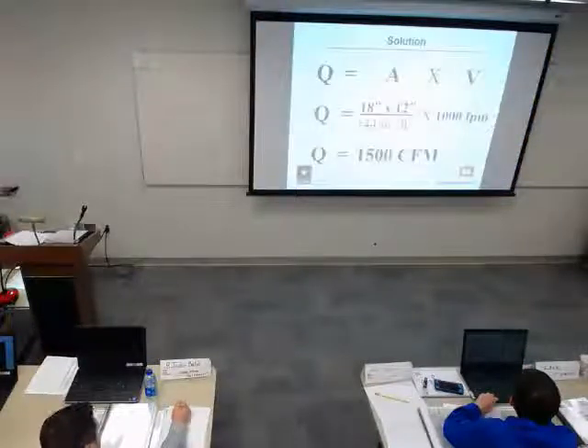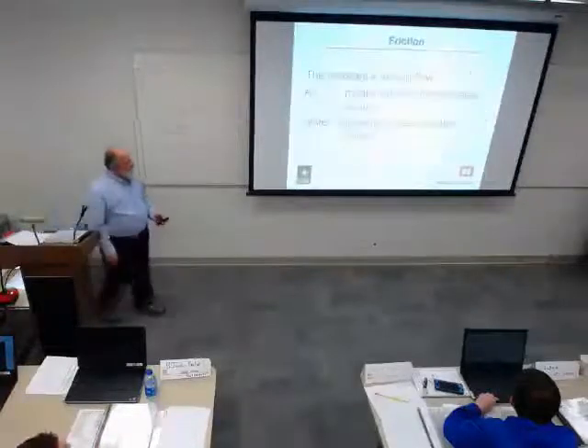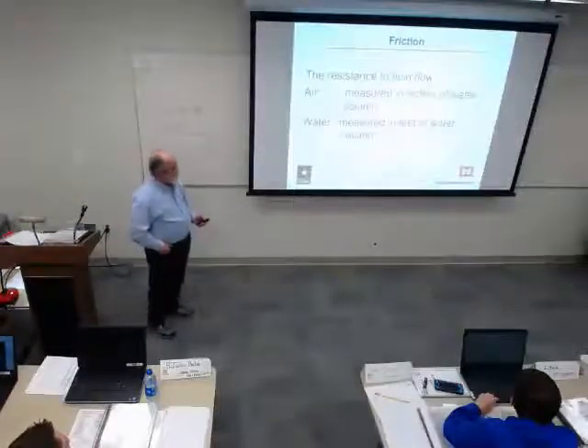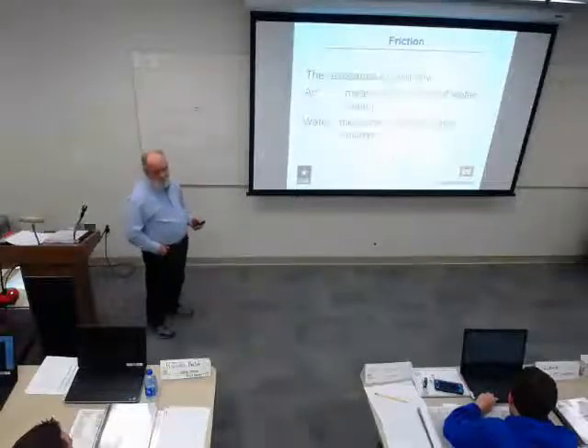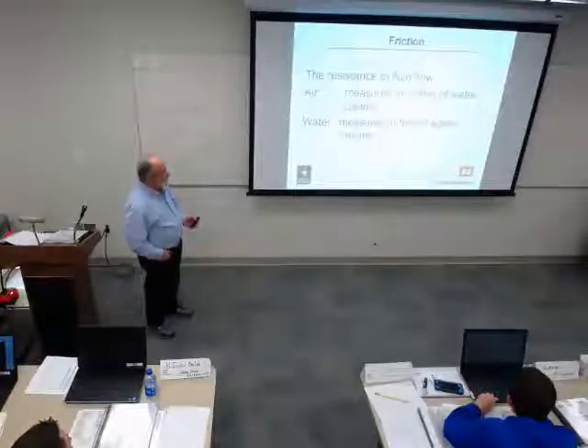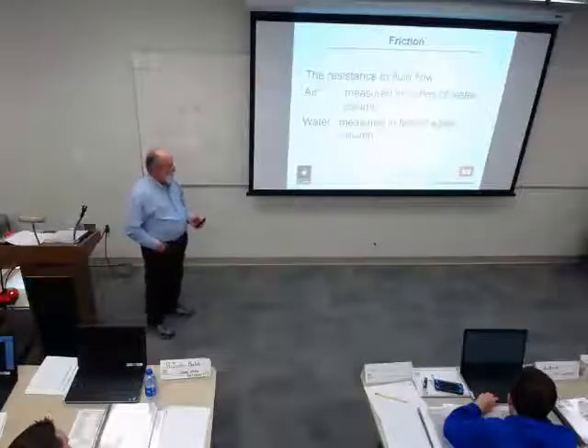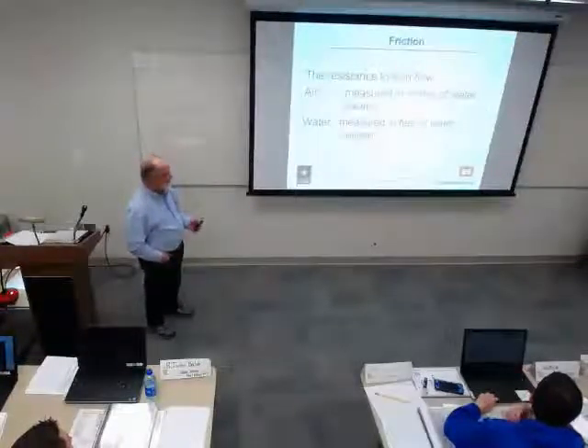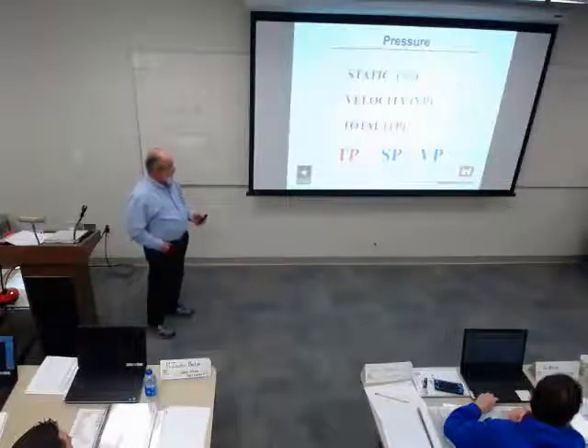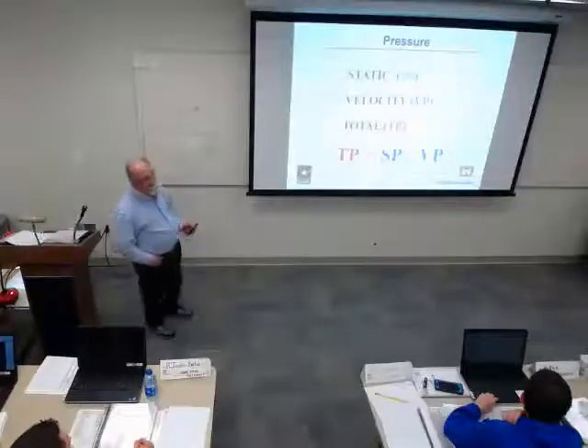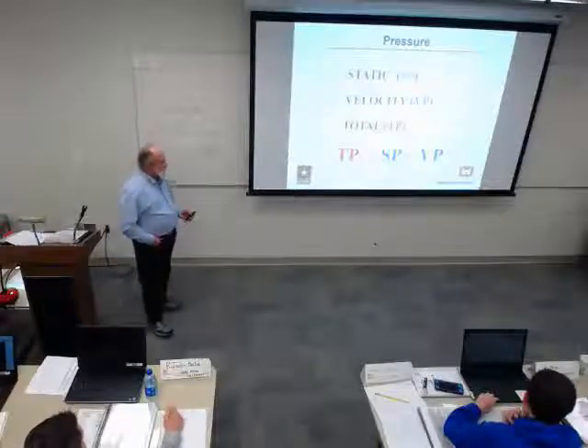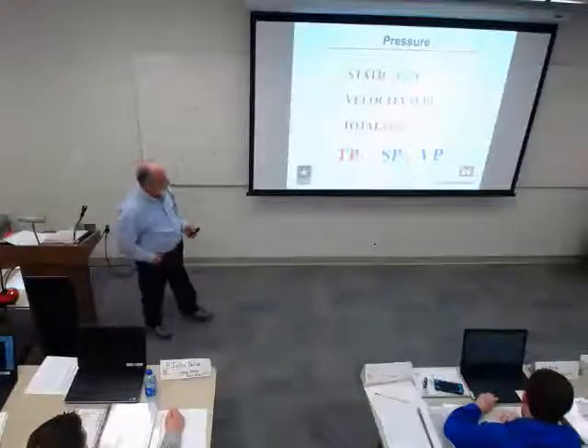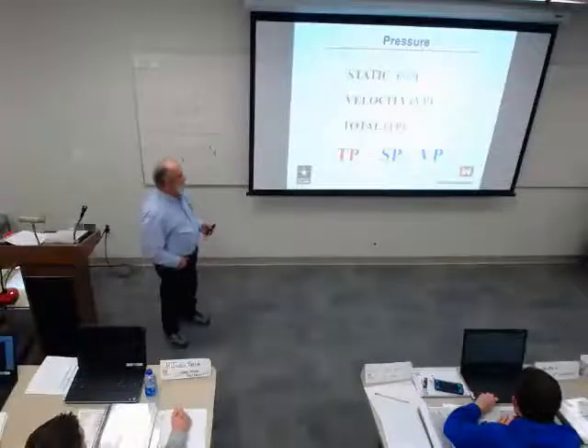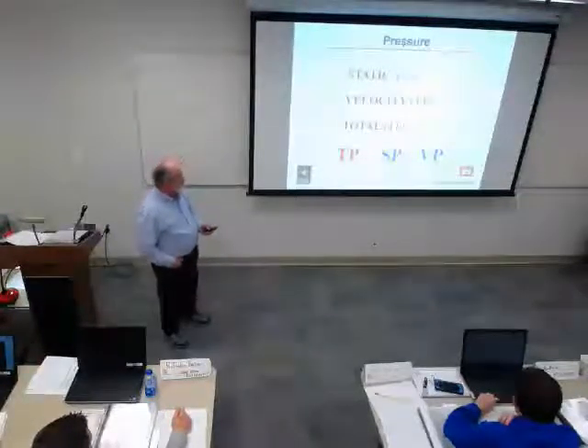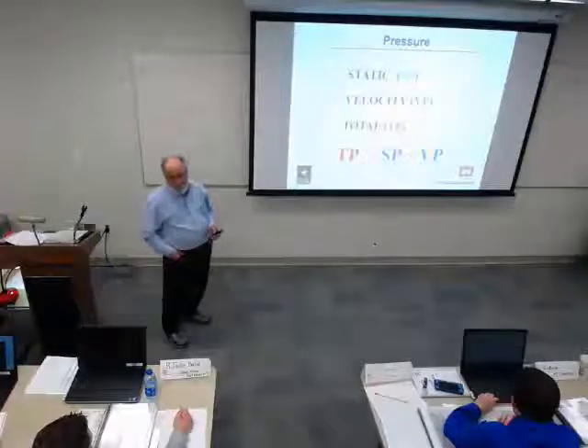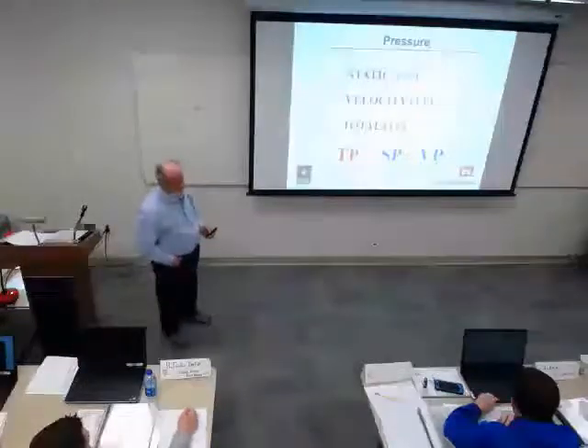All right, back to our story here. Resistance to airflow, or fluid flow in air, we measure in inches of water column. And for water, we measure that in feet of water column. Pressure. I'm going to start with the bottom and work up. Total pressure, that's TP, is equal to static pressure plus velocity pressure. Velocity pressure is the VP, and static pressure is the SP.